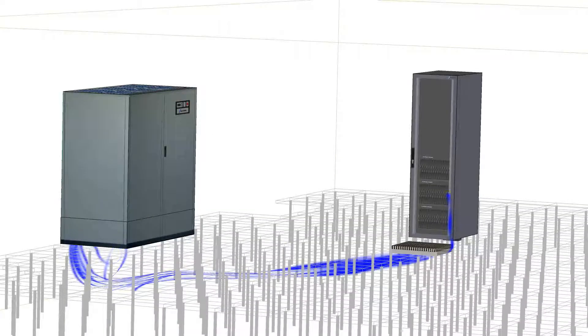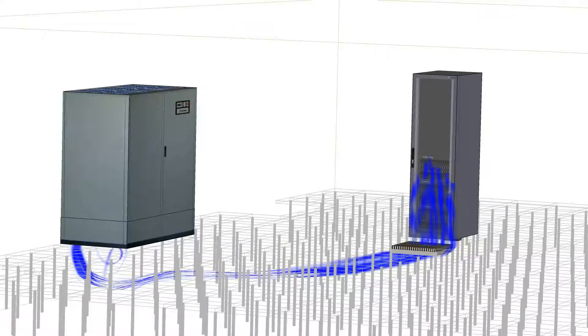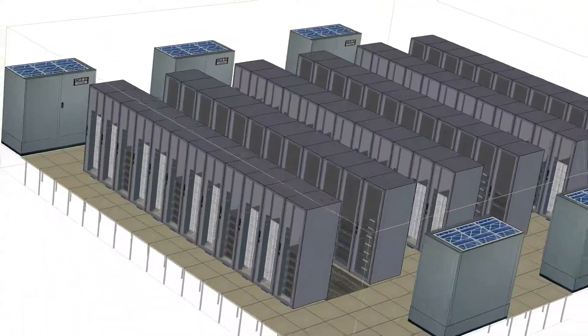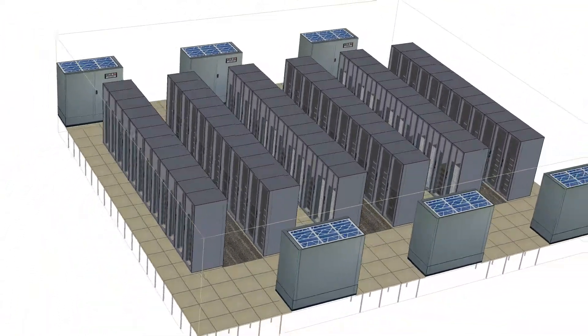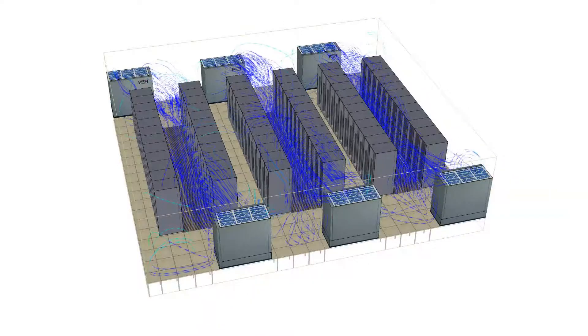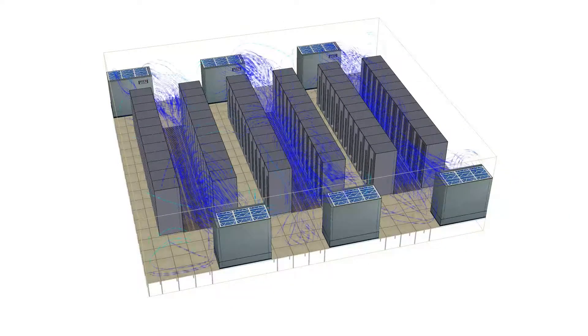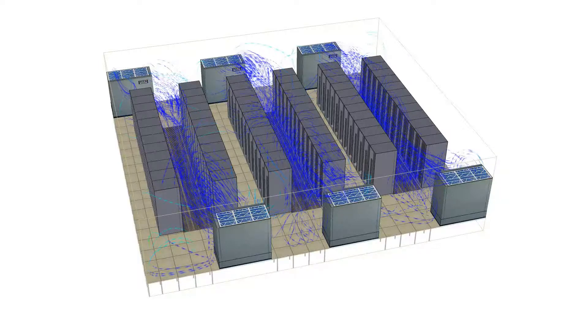Bypass airflow refers to any air in the data centre that returns to the air conditioning units before supplying IT equipment. The sole purpose of airflow supplied by the cooling units is to cool down computer equipment. Therefore, any airflow that returns before doing so is wasted and reduces efficiency.